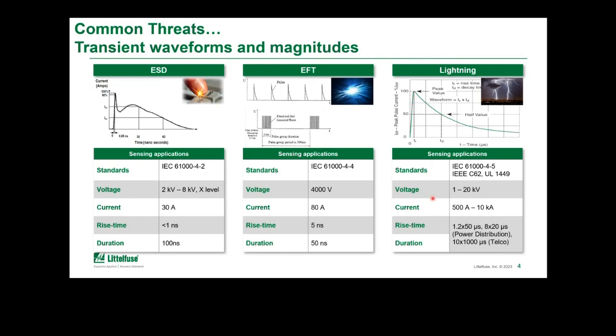Now, there are other waveforms that are used. There are certain components that are referenced, different waveforms, telecommunications systems kind of have their own different waveforms that range anywhere from a 10 by 1000 microsecond waveform to a 2 by 10 to a 5 by 350 and so on. Now, the voltage levels that can occur in these lightning events or in these test simulations can range anywhere from about 1 kilovolt, in some cases 500 volts, but then all the way up to a 20,000 volt event. And this can result in anywhere from 500 to 10,000 amps of transient current. So this is a lot of energy to try to handle and make sure that we're not resulting in damage to the end equipment that we're trying to protect.